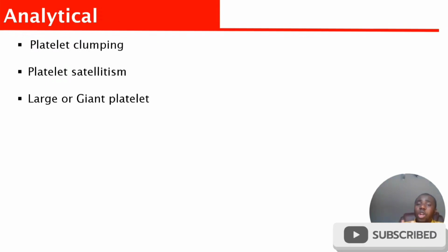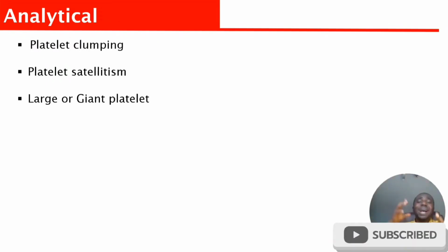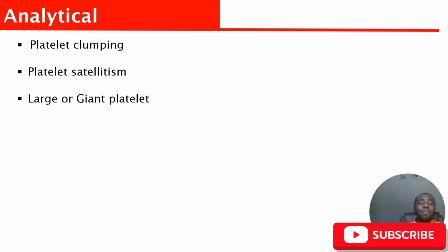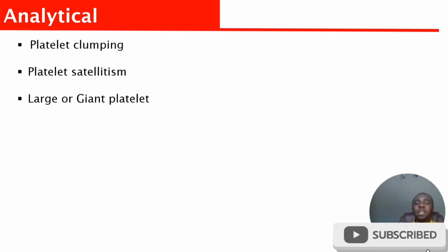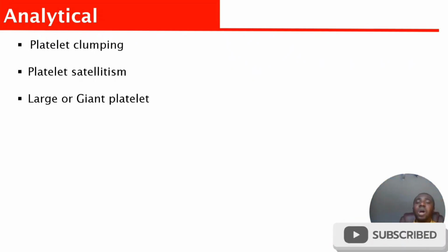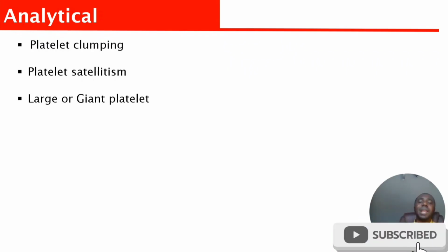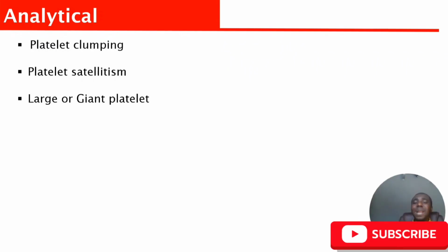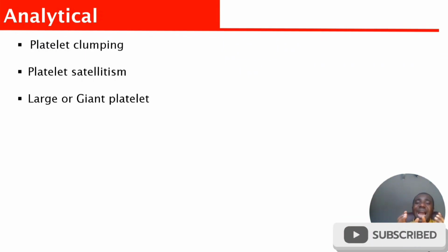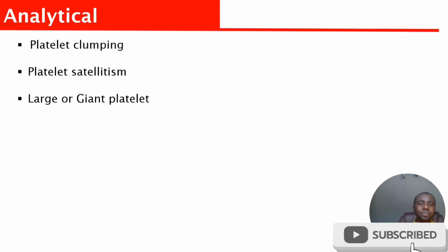I hope that makes sense. Although some analyzers might start giving you a suggestion once they notice abnormal sizes, and say suspect giant platelets or large platelets, as the case may be. But anyway, large platelet means that as the cell passes through the aperture, the analyzer may not be able to detect, measure, or count it as a platelet, because it might think it's not a platelet since the size is bigger than the actual normal platelet. I hope that makes sense.